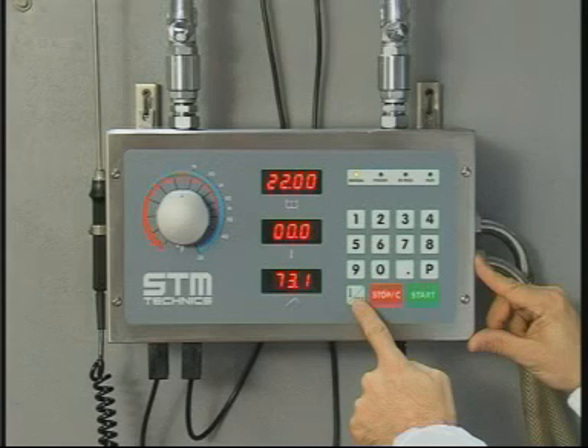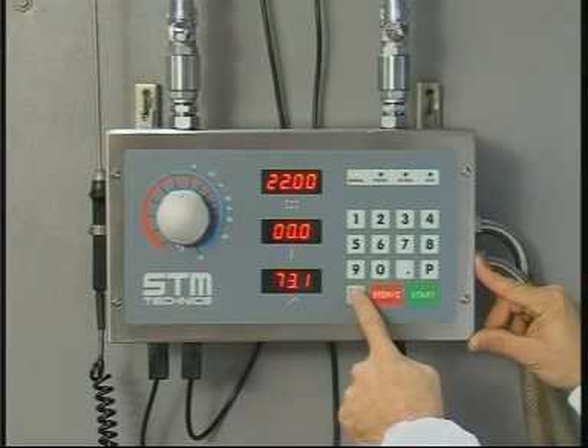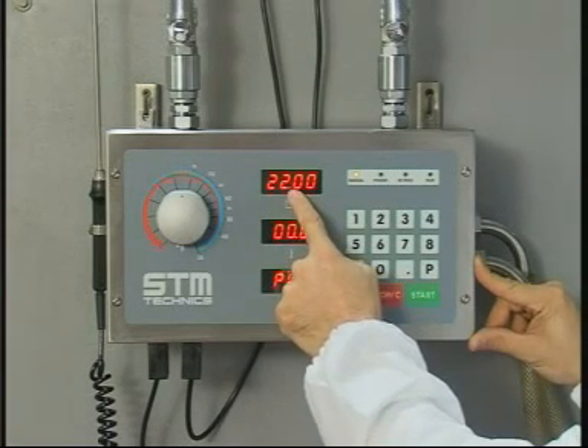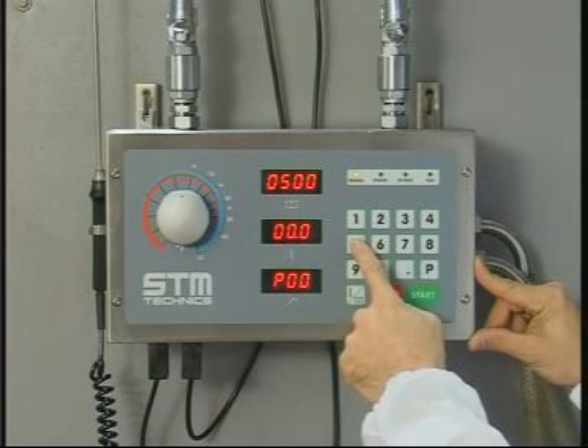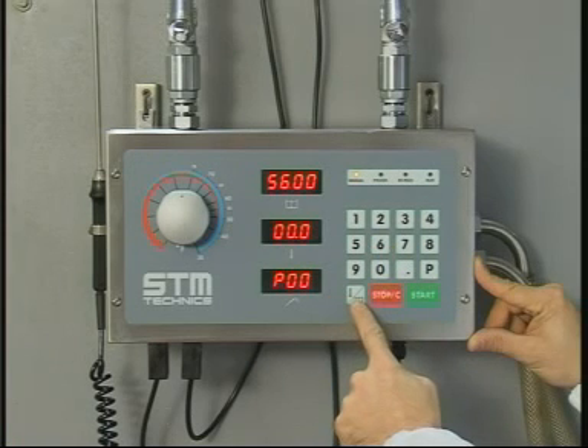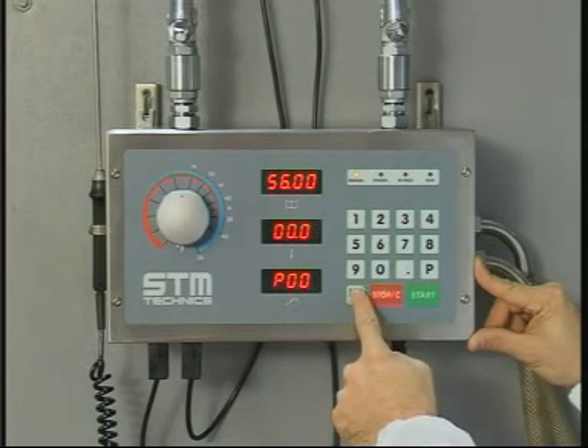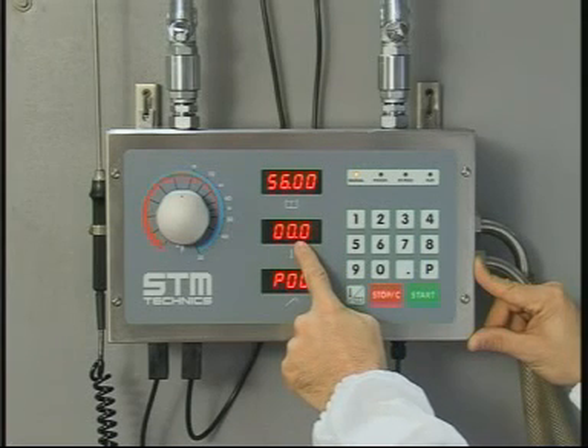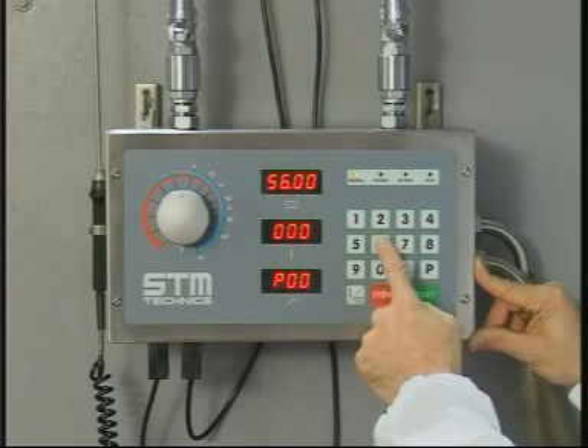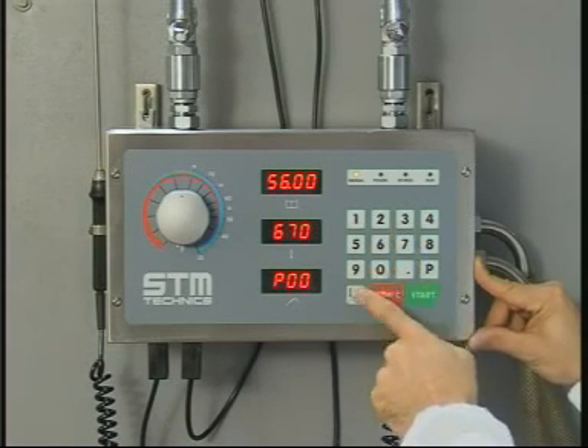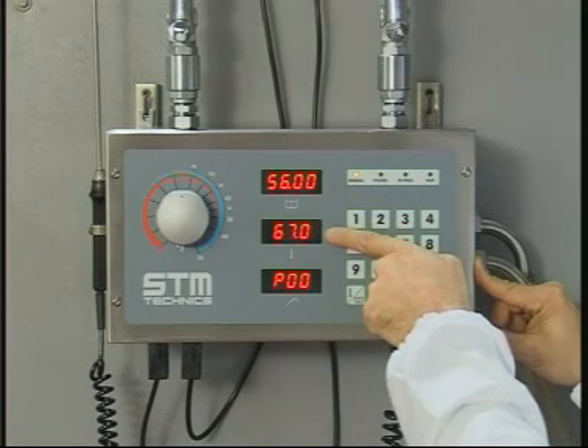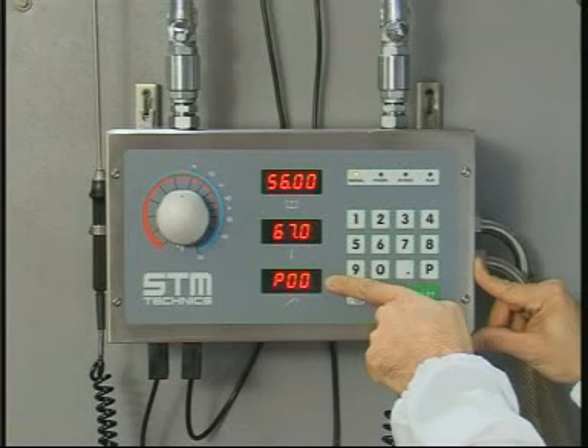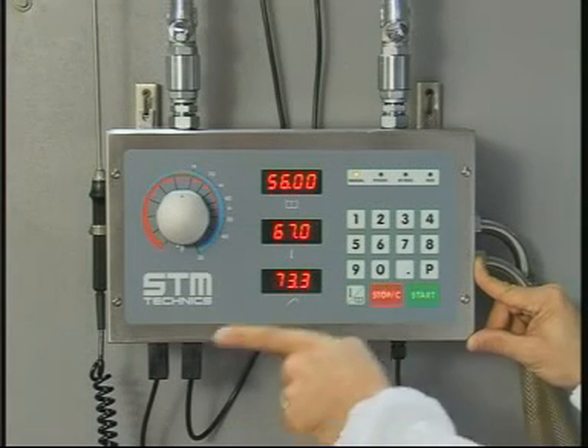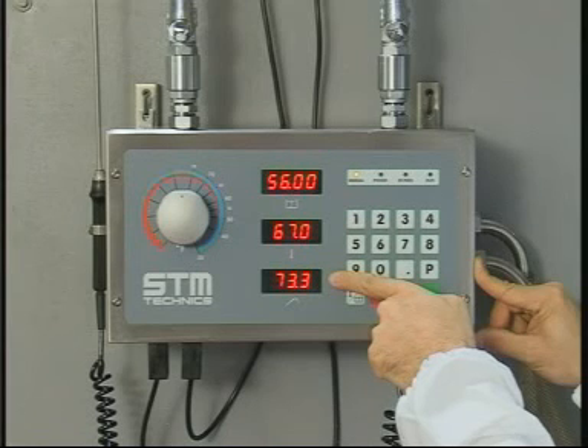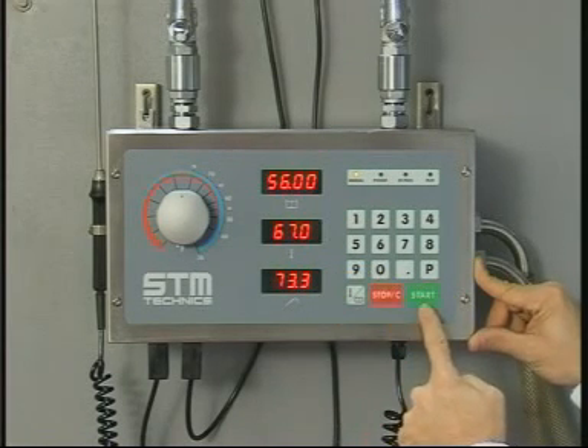P00. During the manual operation, by pressing the quantity temperature key, the decimal point of the upper display begins flashing and the desired quantity can be programmed. Pressing again the quantity temperature key, the decimal point of the central display begins flashing and the desired temperature can be programmed. After some seconds, the writing P00 disappears on the lower display and the temperature of the external probe reappears. Meanwhile, the programmed temperature remains visible in the central display.